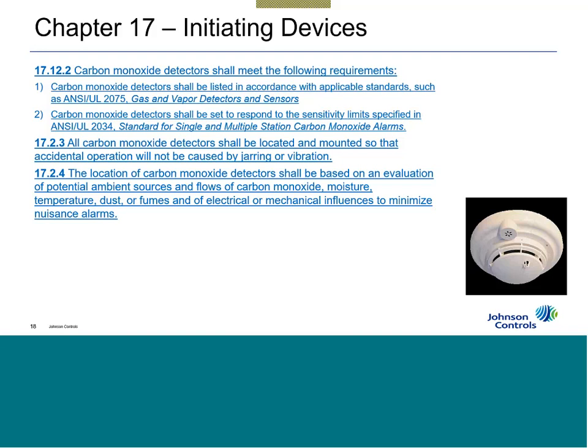And our devices will send a signal to the fire alarm control unit and indicate when they're getting close to end of life, as far as a year out, and they need to be replaced. And for those that don't know, these devices, these cartridges, are very easy to replace, and the end user can do it. There's no tools, no programming that needs to be done, no switches that need to be set. You can just pop it out, pop a new one in, the system recognizes it, and away you go.